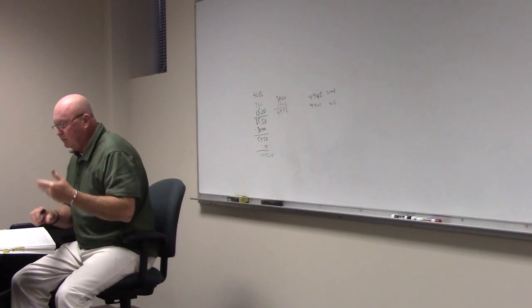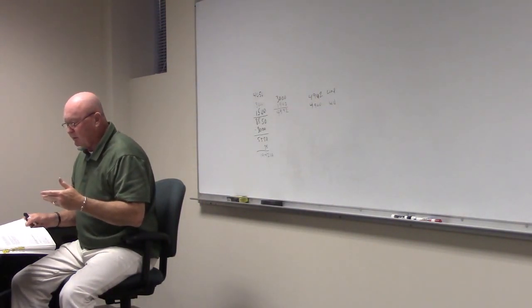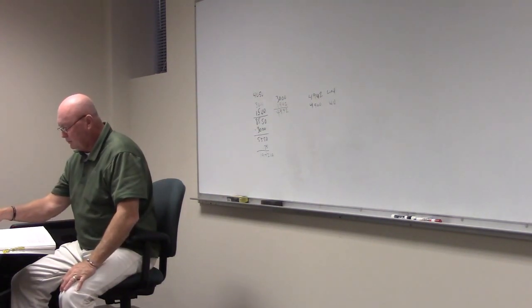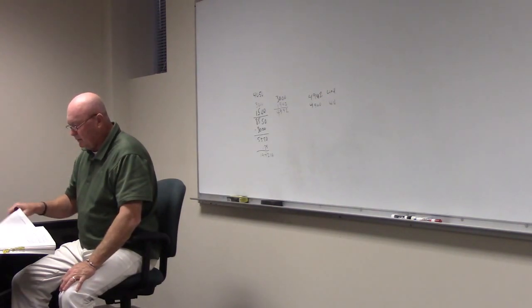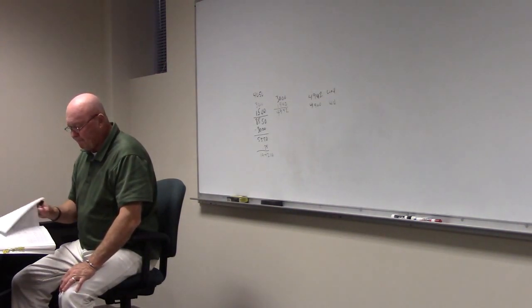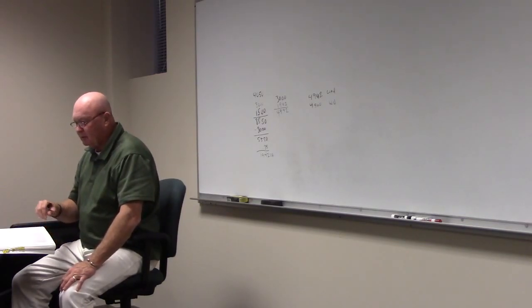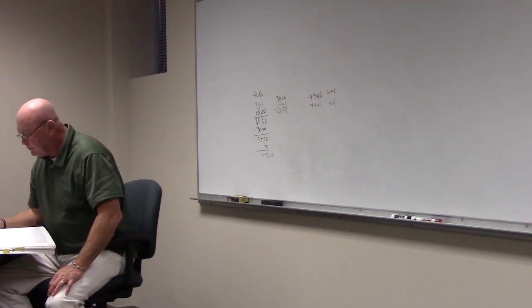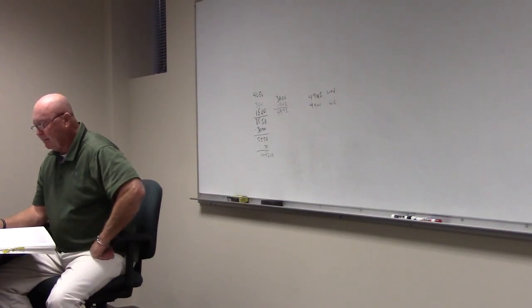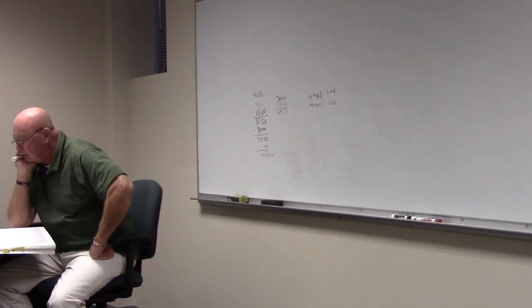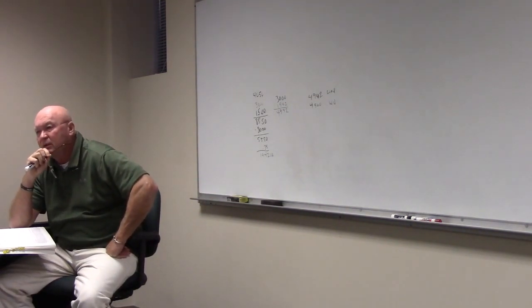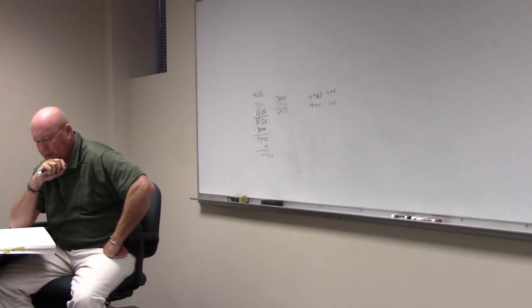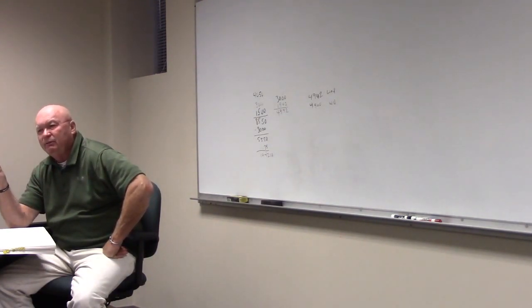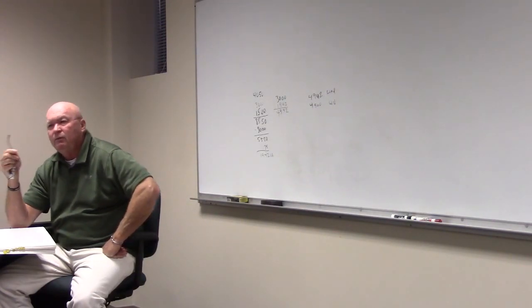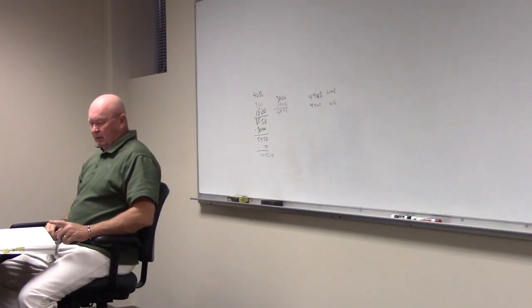Step 11. Calculate the load of the range. Okay. What was the load on the range? What did it say in our example? Go back and look at it. Tell me what it said. What did it say the range was? 12 kW? Is that what it said? Well, how do we calculate? Does that 12 kW become 12,000? No, because there's a table for ranges. 220.55. There's 3 columns. How many ranges do we have to start with? How many do we have? The one. 1. Okay.